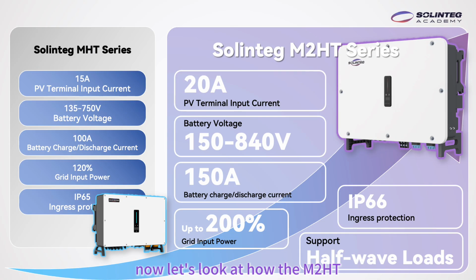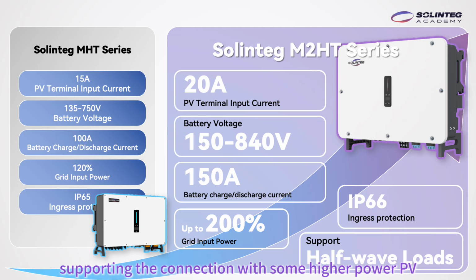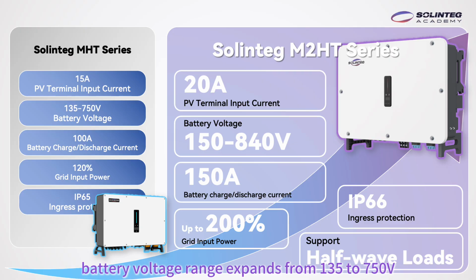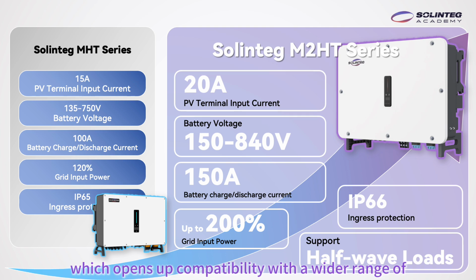Now let's look at how the M2HT series improves on its predecessor, the first generation of 25 to 50 kilowatt hybrid inverter. The upgrades are meaningful across the board. PV terminal input current increases from 15 amps to 20 amps, supporting the connection with some higher power PV panels. Battery voltage range expands from 135 to 750 volts, up to 150 to 840 volts, which opens up compatibility with a wider range of battery configurations.